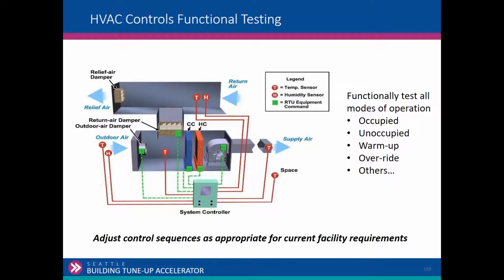Functional testing. So for the equipment that you're going to test, at a minimum, you're going to want to functionally test the occupied mode, right? So in the occupied mode, the fan runs continuous at a constant speed. On a call for heating, the gas furnace fires and delivers hot air to the space. On a call for cooling, if the outside air temperature is less than the economizer set point temperature, open the outside air damper. There might be a discharge air sensor on that. If it's greater than, the outside air damper should be at minimum position and energize mechanical cooling. So just use your judgment for the sequence of operation for that type of equipment.